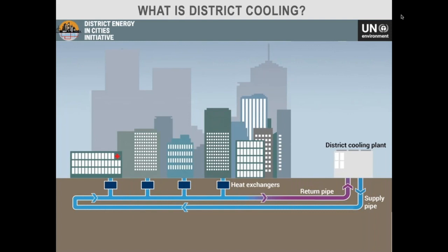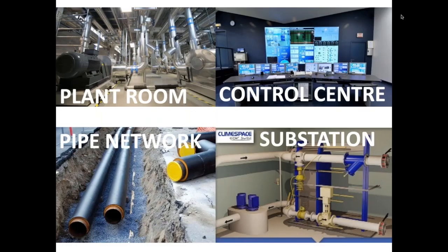One technology we're promoting is district cooling. For anyone who doesn't know what district cooling is, it essentially centralizes cooling within a neighborhood: rather than each building having its own ACs or chillers, we centralize that into one plant and provide chilled water through underground pipes to each building, where heat exchangers extract the chilled water. This includes a plant room with chillers in the central plant, a control center to optimize the network, a highly insulated underground pipe network to prevent losses, and a substation — which you might find underneath or next to a building — that links the district cooling supply pipe with the building's internal cooling system.